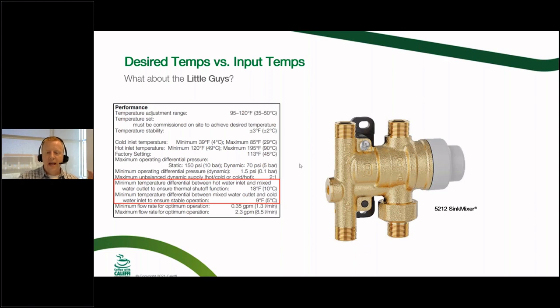So this is an ASSE 1070 mixing valve. This is a point of use mixing valve. This is going to go underneath your faucets. It's going to be the anti-scald mixing valve that we all talk about. The idea with this valve is that it has the ability to completely shut off the hot side in the event of a cold water failure, a shut off of the cold water for whatever reason. Again, preventing scalding, preventing anybody from getting hurt. But in order for that thermal shutoff function to work, you need to have the temperature of the hot inlet 18 degrees higher than the desired mixed outlet temperature.